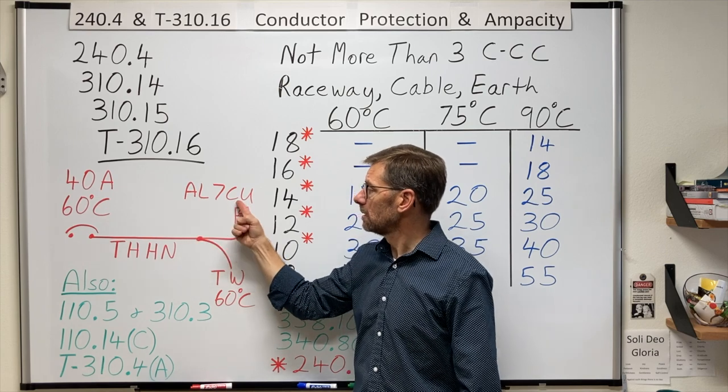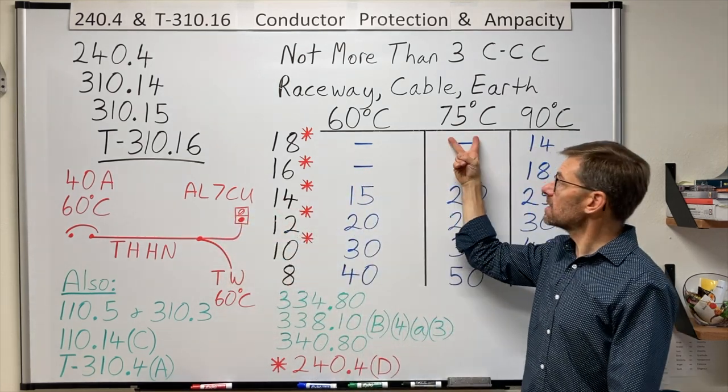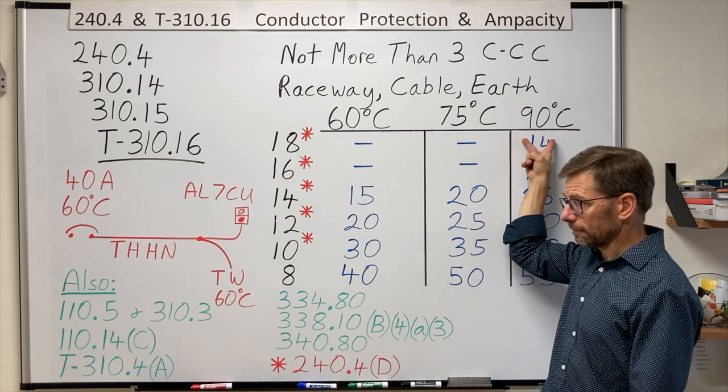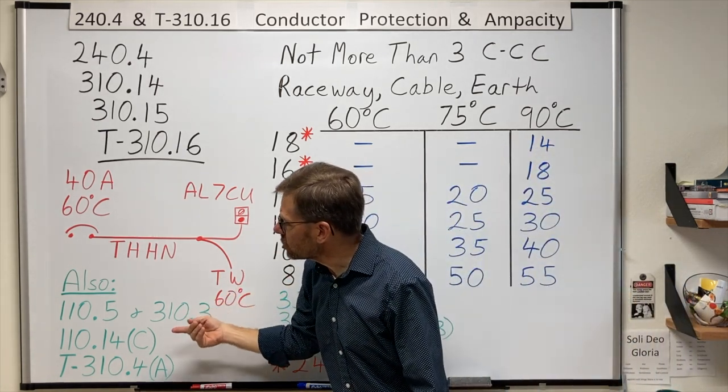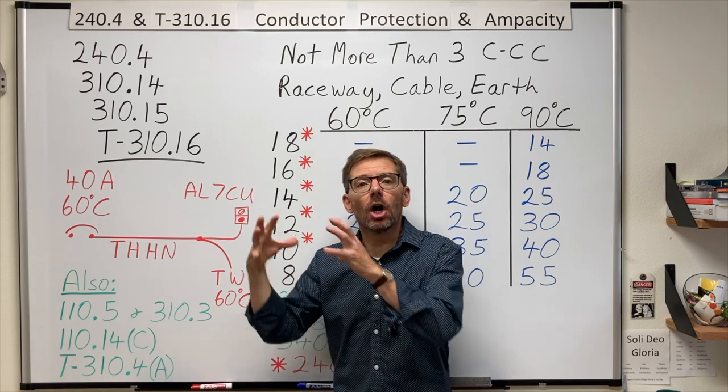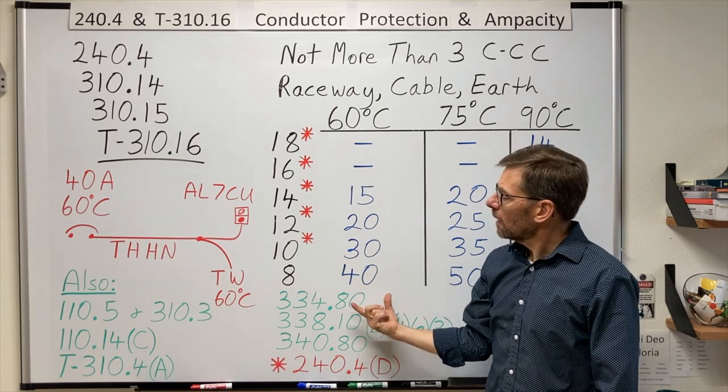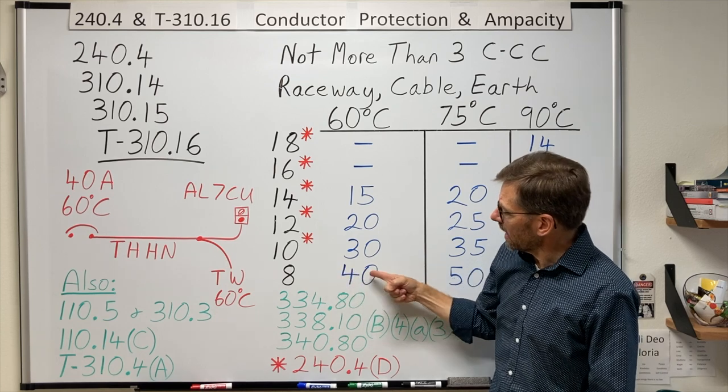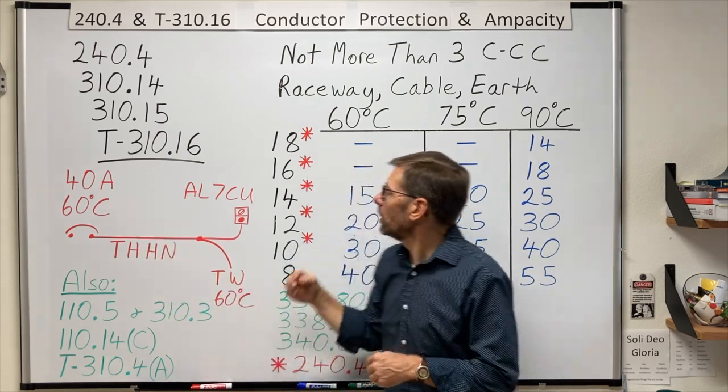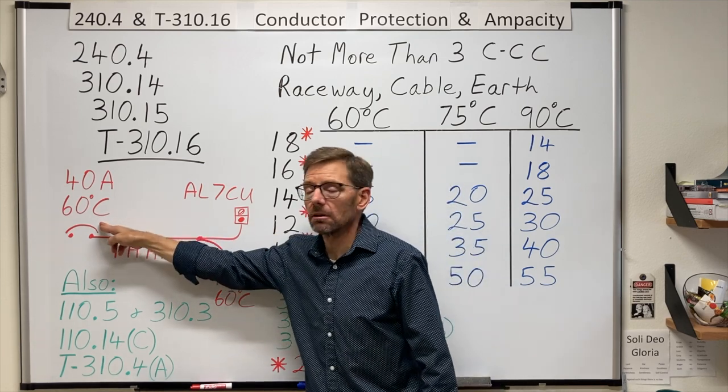And there's a number in there. A 7 would indicate it's rated for 75 degrees Celsius. And a 9 would indicate 90 degree rating. Now, there is a general rule in 110.14c1a that says for conductors 100 amps and less, you're limited to the ampacity in the 60 degree column. Which would mean here that 40 amps I'd need a number 8. And if I did that, I put a number 8 in there. That conductor, because it has more copper in it, would not get as hot. And therefore, it couldn't overheat the connected terminations conductor device.